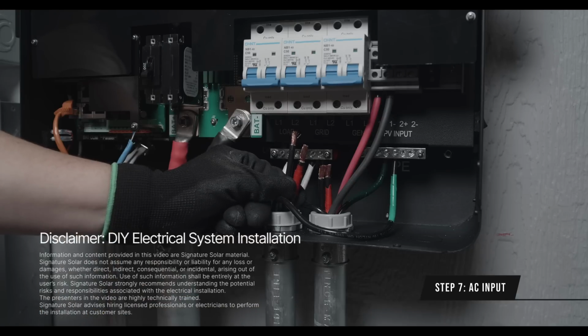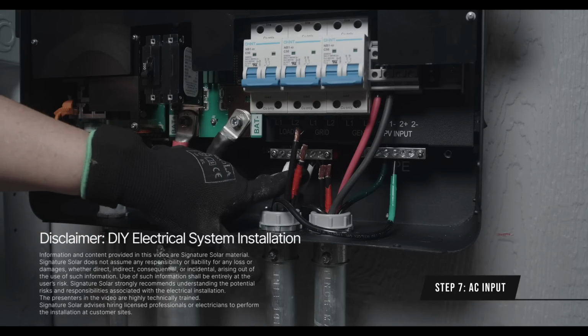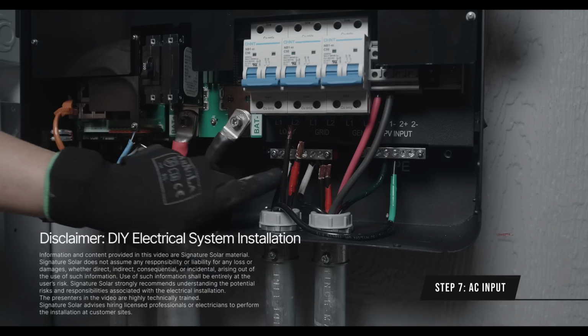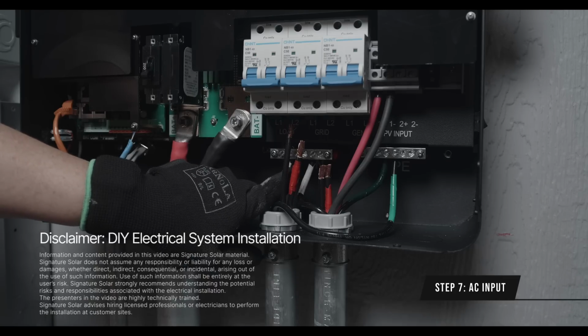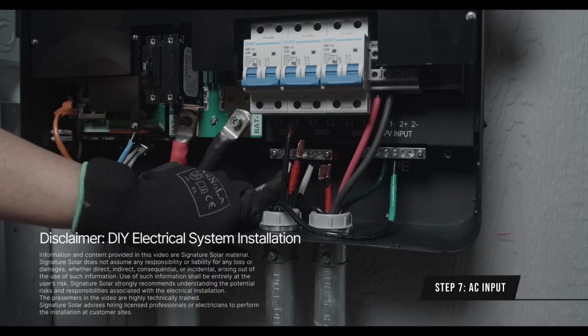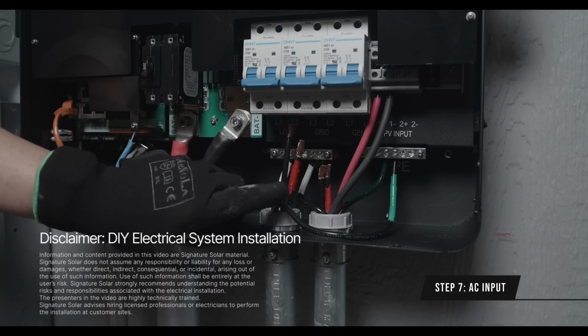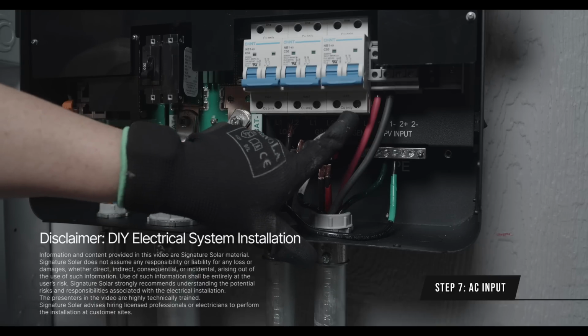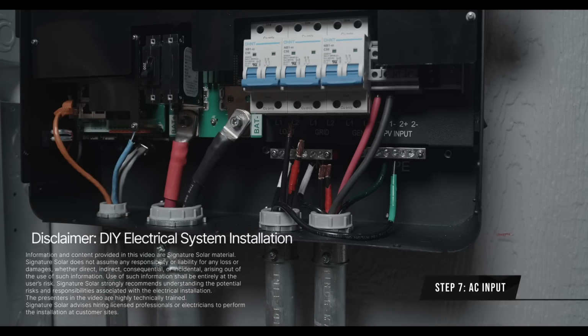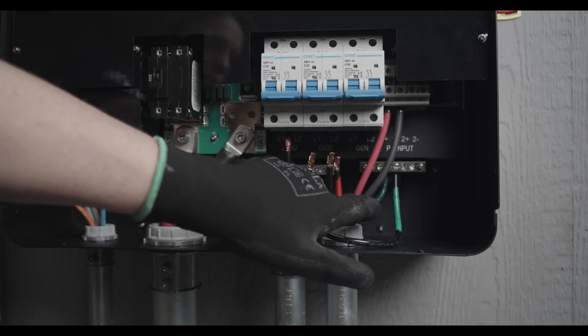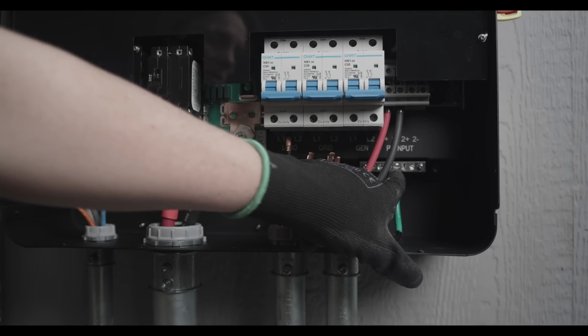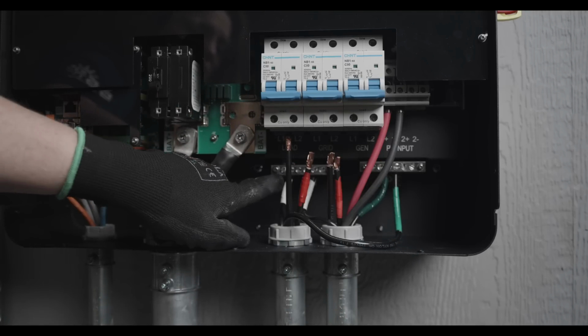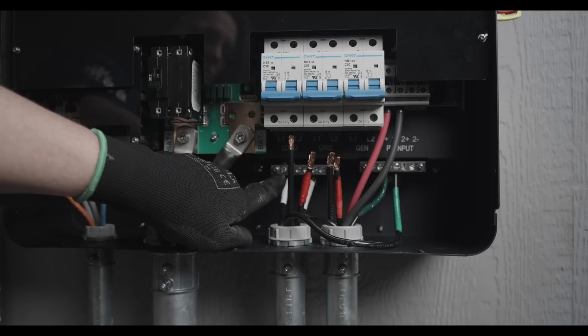Use 8 gauge for your grid, generator, and load connections torqued to 18 inch-pounds or 2 Newton meters. Connect the AC output ground to the PE bus bar. So here we have our line 1 and our line 2 for our loads that go to our panel. Here's where we'll connect our grid, line 1 and line 2, and these are our generator connections, line 1 and line 2. We have, of course, our grounds coming to our PE bus bar here, and all of our neutral connections will go to our neutral bus bar below.